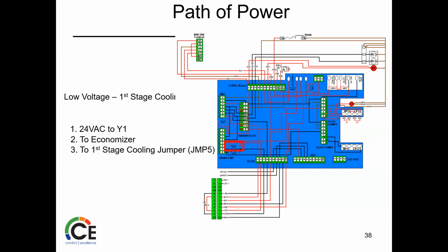Again, looks to make sure that jumper's intact. Goes over to number 4, like I talked about, jumps to 5, runs through high pressure, low pressure. If they're satisfied, hits 6, contactors engaged. So if you have power through all that, then what's the most logical thing, right? There's a possibility of a bad contactor, because we have power all the way up to there, we're only leaving the one thing left.